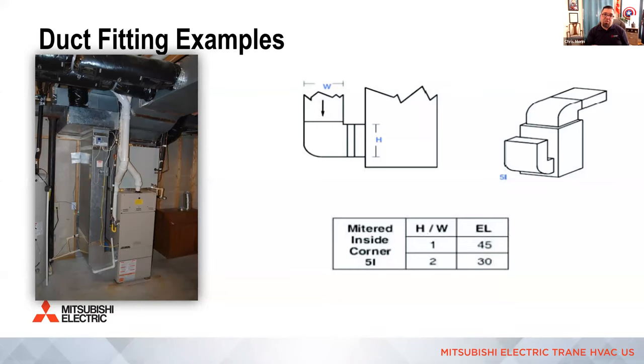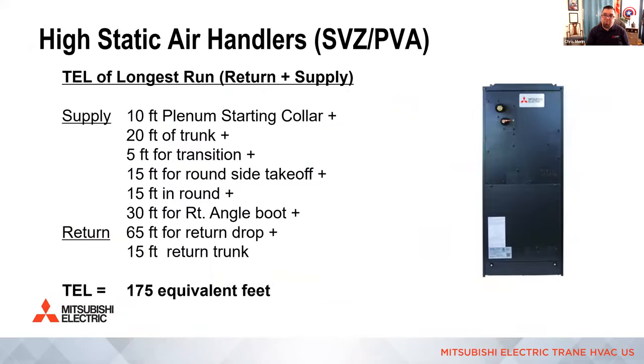So if it's easier for the air to make the turn, it's much better for the system when it comes to the health of the system and how noisy it's going to be and how much electricity it's going to use. So in this example, I'm going to keep these numbers really small and just walk you through. If you can imagine the basement duct layout of a vertical air handler, and we had a box coming off the top of it, and that first plenum starting collar going into a trunk is the first fitting we account for on the supply. And if it's got an internal mitered on the inside radius of any sort, then it's going to be a 10-foot plenum starting collar, a very low pressure loss to get the air into that trunk.